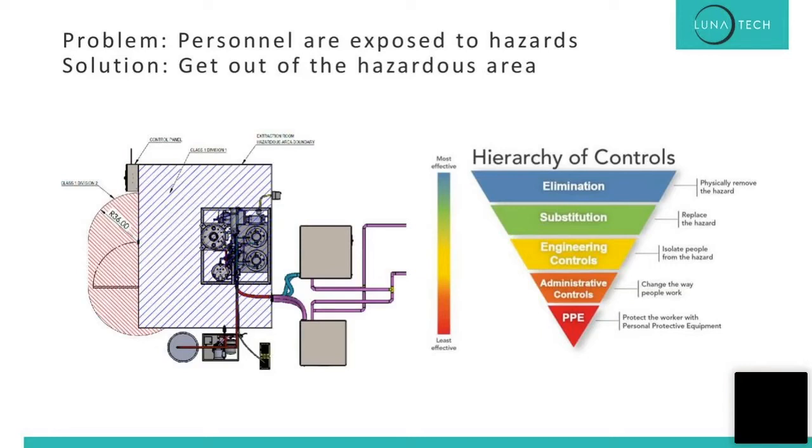One of the benefits of our equipment too is it ties into that alarm monitor that monitors the gases. So it will shut down and isolate all of the vessels if there even was a leak. So our system minimizes the risk even when they're in there as well. Yeah, exactly. And we're one of the only systems available on the market that can tie into that alarm and shut down operation once it senses gas. Which is really surprising because, per the new NFPA code, everything inside your extraction booth, any electrical, has to be tied into the gas monitoring system now on an interlock. Anyway, it's an important safety feature.